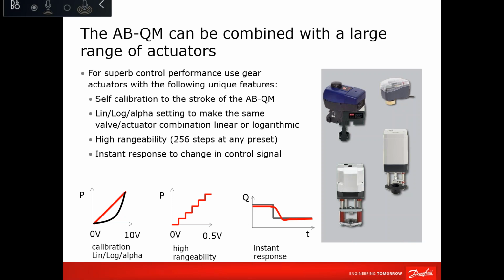Now, this is the case of the actuator used up to the DN32. If we take the actuator used for the DN40 and bigger, we have 1,024 steps, which means, again, the bigger the stroke length, you need a higher number of steps to achieve the same control precision, which is 1,000 to 1. This is the rangeability that we are specifying.